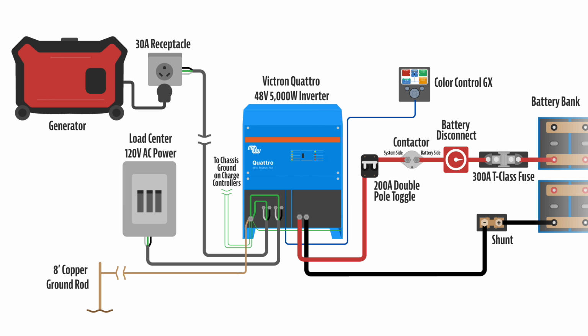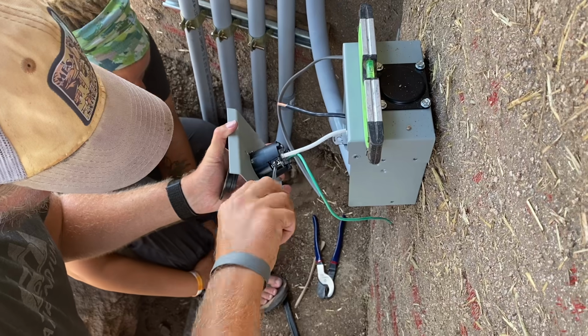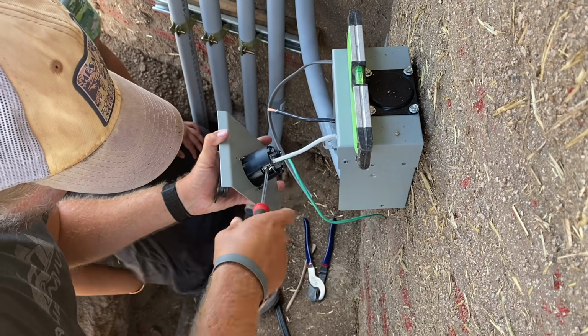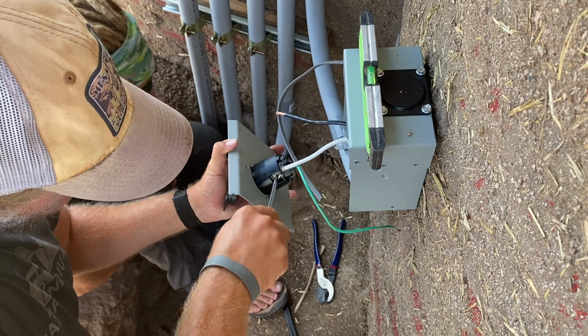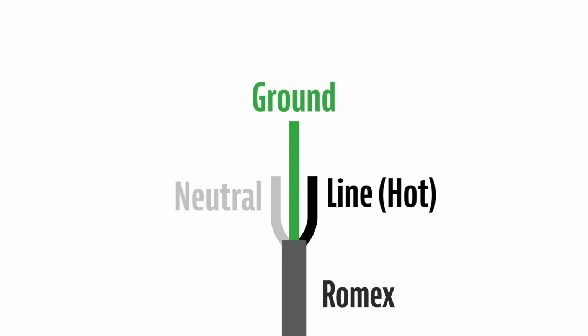If you want to charge your batteries via a generator, you can run some wire to the AC in one connection, then connect the other side of the wire to a 30 amp plug. Note that we're now in 3 wire territory: black is line, white is neutral, and green is ground. Also know that you'll need to adjust the charging settings of the inverter based on your generator size.